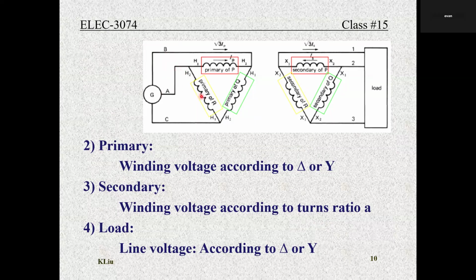The relationship between the currents is going to employ that square root 3. Line current will equal phase current times square root 3. In the star, it's the opposite: the currents are the same, and the voltages depend on the square root 3 relation.